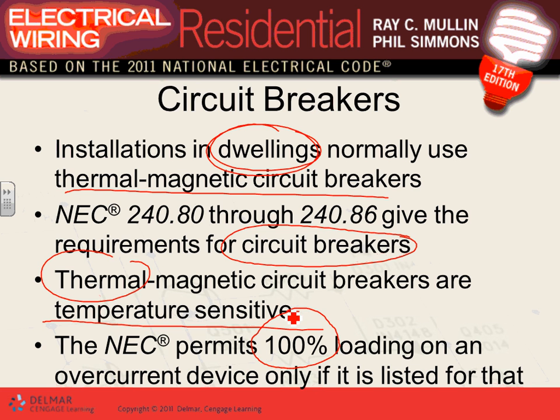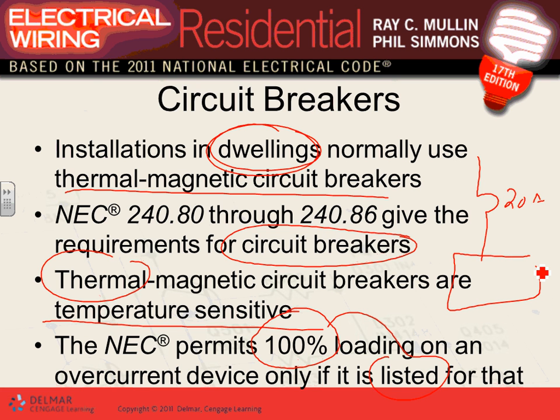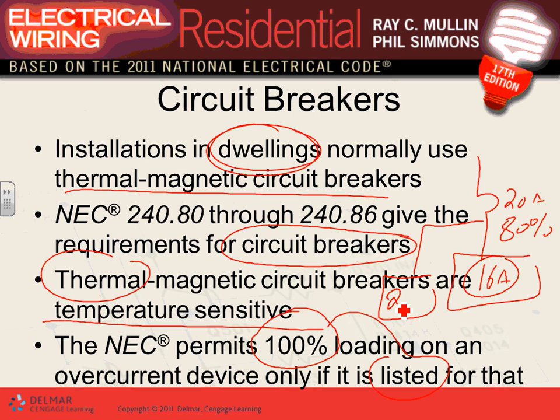Loading a circuit breaker at 100% continuously is only for listed 100%-rated equipment. For example, a 20-amp circuit breaker — you can only carry 80% of that, which is 16 amps, continuously. Unless the circuit breaker is marked as 100%-rated, it is rated for 80% continuous. Non-continuously, you can carry the full 20 amps.